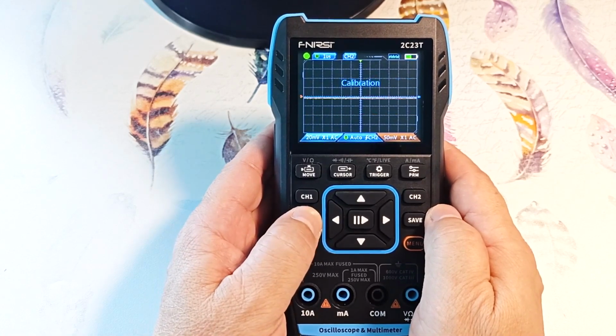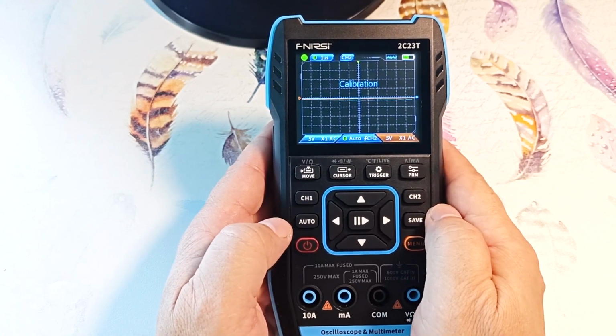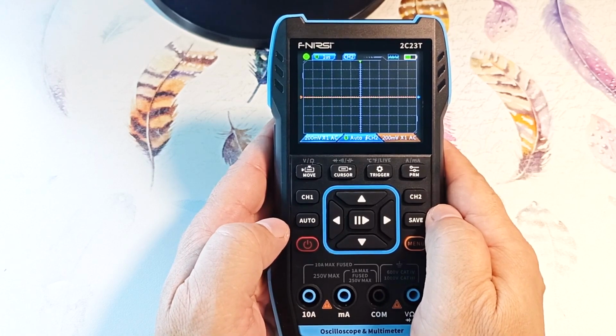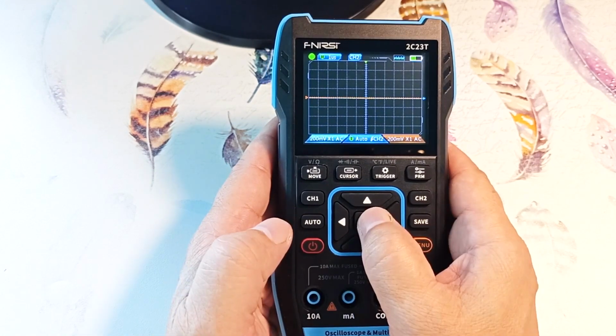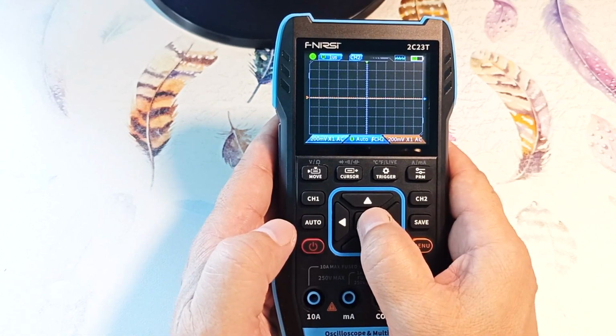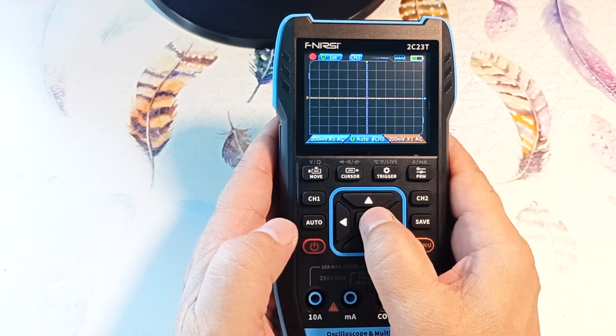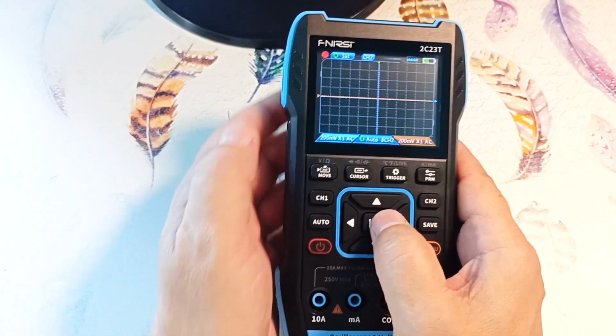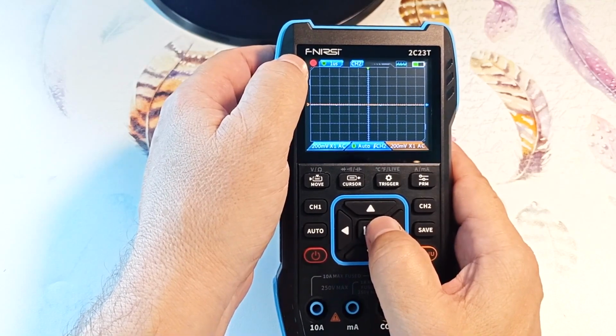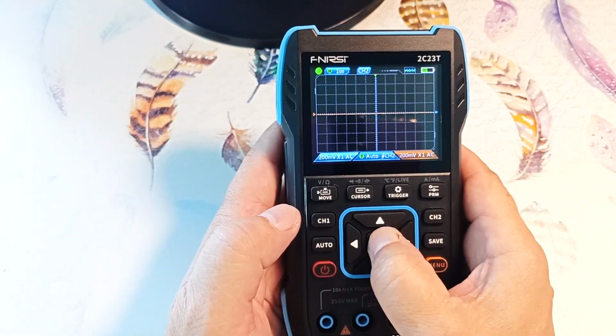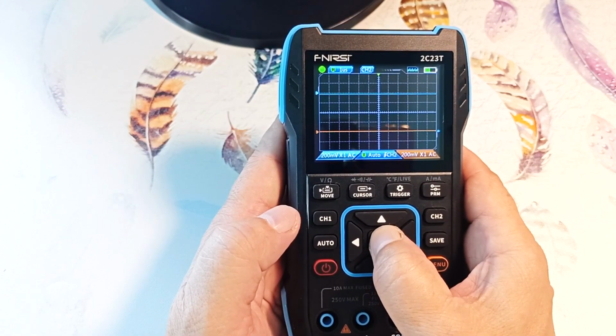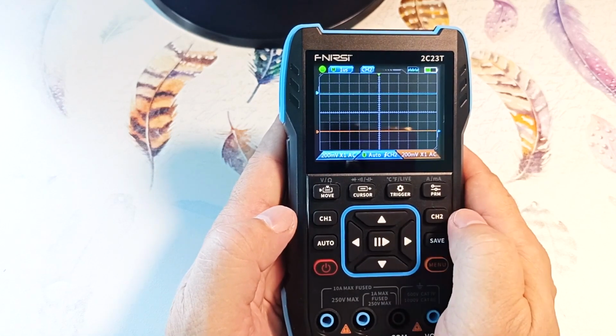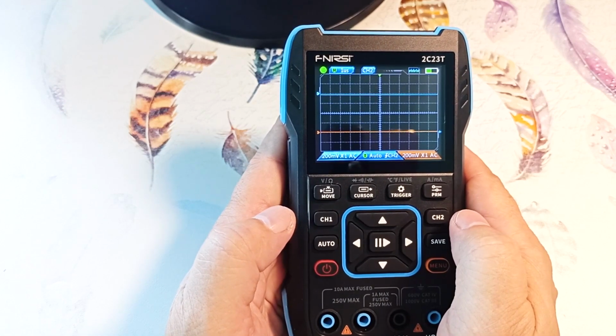Long hold, line calibration. In this case, both lines appear in the center of the screen. A short press on the middle joystick button enables screen capture, and the waveform stops. At the same time, the red dot lights up. Holding the center key for a long time will center the lines. But the level of the lines will be different, the same as you see on the screen.